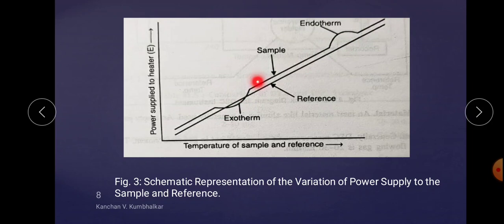Now again at this temperature the reaction has not occurred here, hence again the demand of power from the heater to the sample and reference is considered equal. It is considered quite equal.